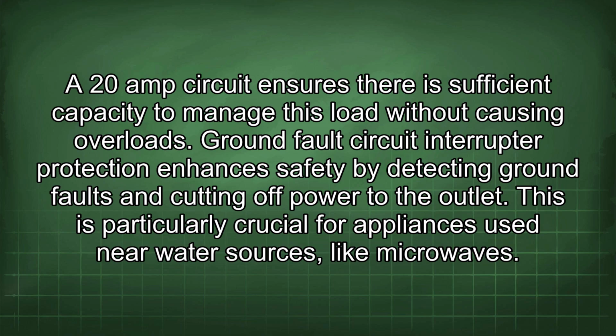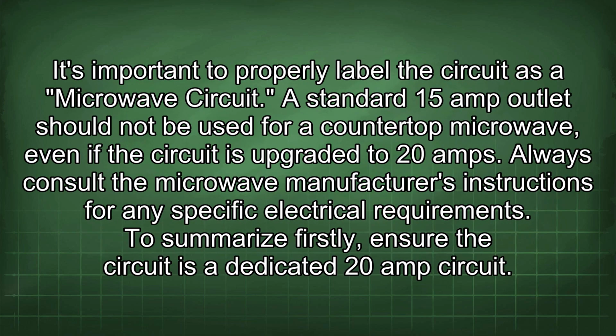Ground fault circuit interrupter protection enhances safety by detecting ground faults and cutting off power to the outlet. This is particularly crucial for appliances used near water sources, like microwaves. It's important to properly label the circuit as a microwave circuit. A standard 15-amp outlet should not be used for a countertop microwave, even if the circuit is upgraded to 20 amps. Always consult the microwave manufacturer's instructions for any specific electrical requirements.